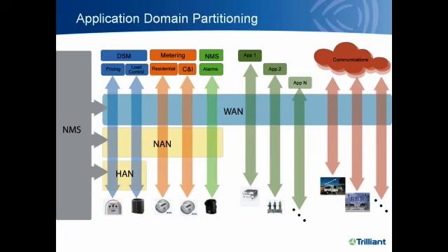For instance, metering applications and demand-side management can be given their own partitions over the neighborhood area network and wide area network tiers to their respective head-end software applications. Additional services, such as distribution automation, device management, and data acquisition, can be isolated to just their respective applications, which may reside in a different part of the utility head-end. And other services, such as mobile workforce data and remote operating system patching, can be given their own isolated partitions that connect to communication networks, such as the IT network or even the internet.